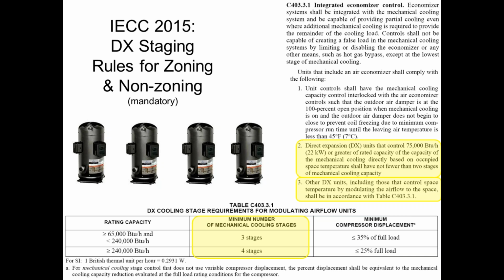And that's a good idea anyway, because the more stages of cooling, the more dampers I have on the system, the more stages I'd like to have to be able to throttle back to. So it makes sense from a logical standpoint, and it's very well code compliant here. Now, with that being said, other people have interpreted number 3 differently, and they say other DX units that modulate airflow to the space. So not that the dampers are the ones modulating the airflow, but that the DX unit itself actually modulates the airflow. So in other words, they're taking a very literal interpretation and saying, if the unit modulates airflow, then you have to do it.